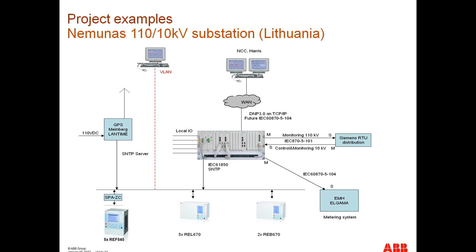This picture is a bigger project from Lithuania, with two network control centers connected to one RTU acting as a gateway, and then again to another gateway RTU with IOs—binary inputs and outputs, as well as analog inputs and outputs. This is all connected to the next RTU at the bay level, collecting information from lots of IEDs you can see here.